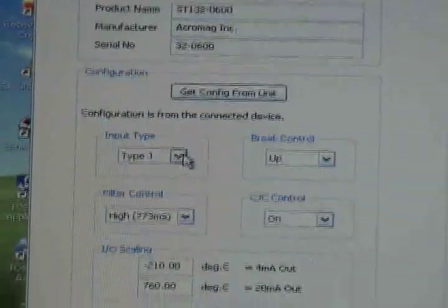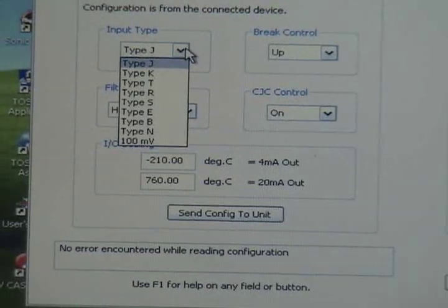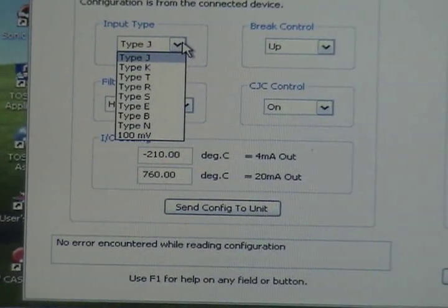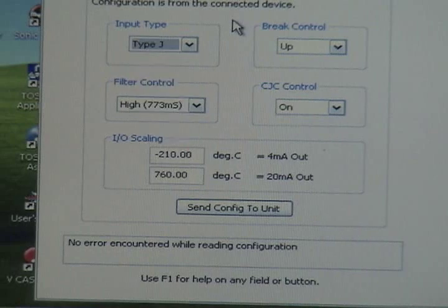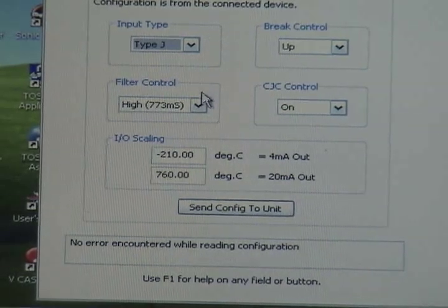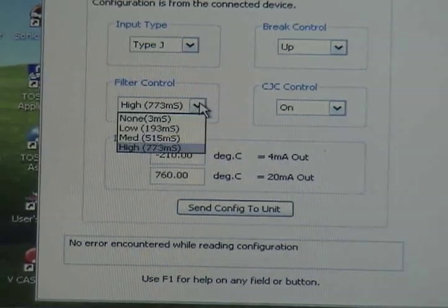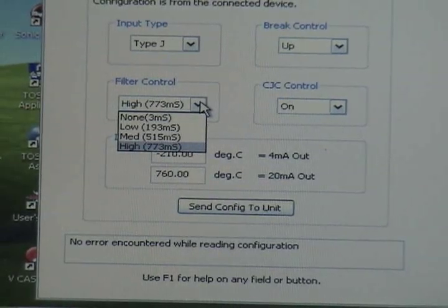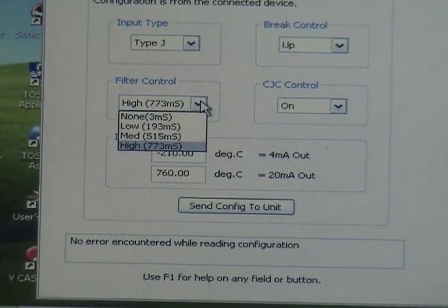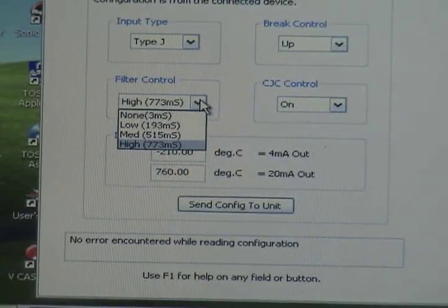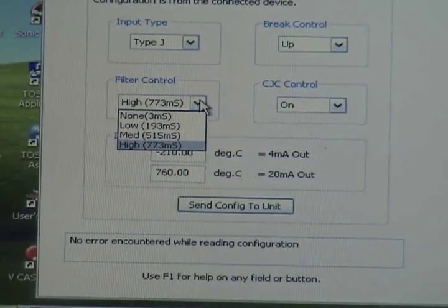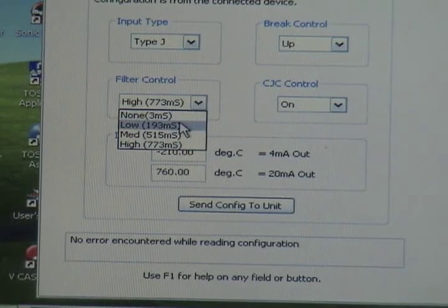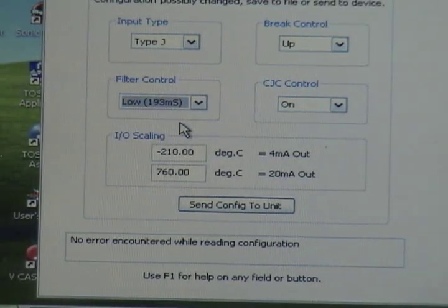Basically what you're seeing right now is the default configuration for an out of the box temperature transmitter. It's set to type J although you can select any one of eight different thermocouple types or millivolts. And for my demo today I'm going to leave it at type J input. For filtering, it's programmable filtering. This unit has a programmable response time as fast as under 3 milliseconds although it ships with a standard response time of about 700 milliseconds. For my demo I'm going to select 193 milliseconds just for show and tell.